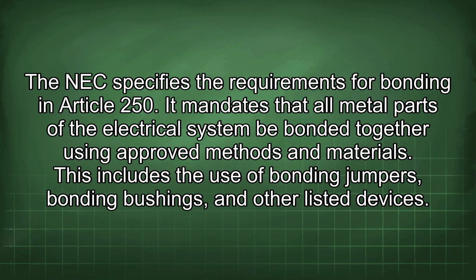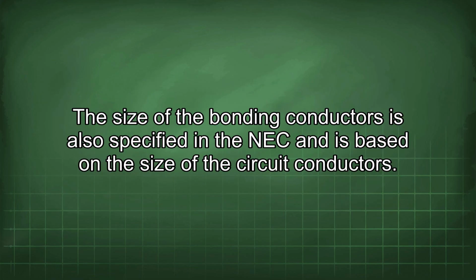The NEC specifies the requirements for bonding in Article 250. It mandates that all metal parts of the electrical system be bonded together using approved methods and materials. This includes the use of bonding jumpers, bonding bushings, and other listed devices.